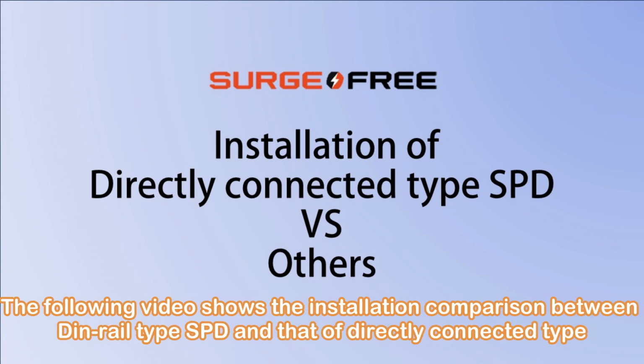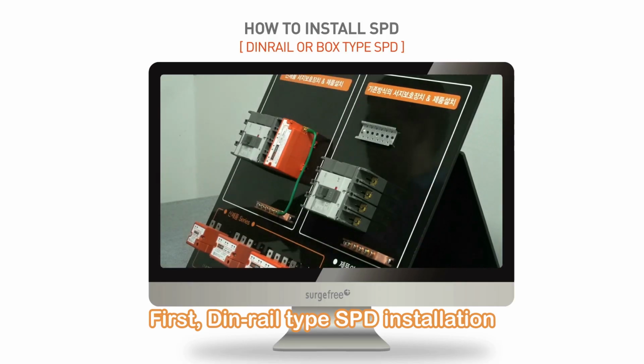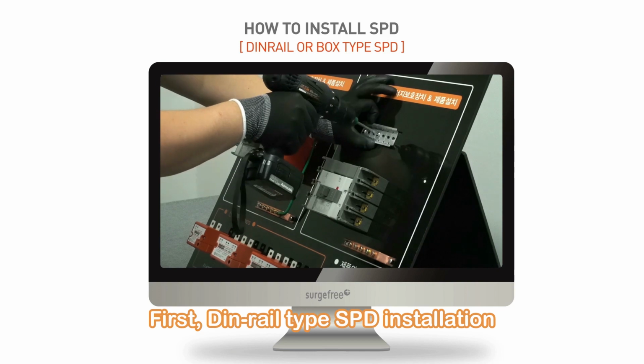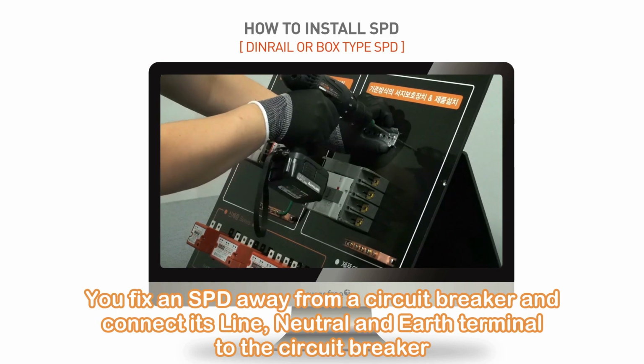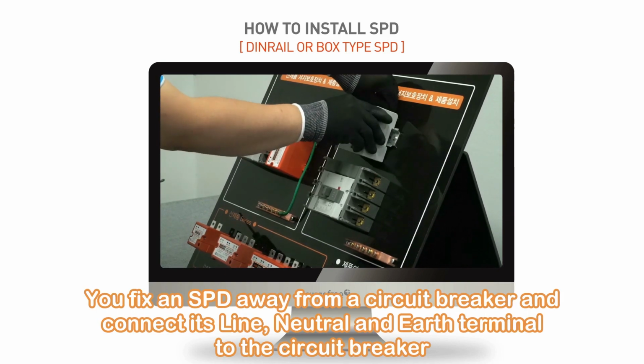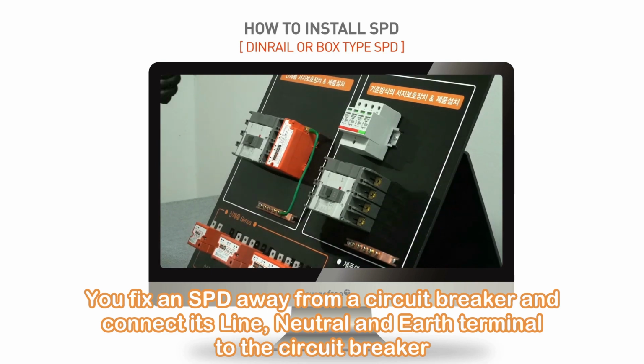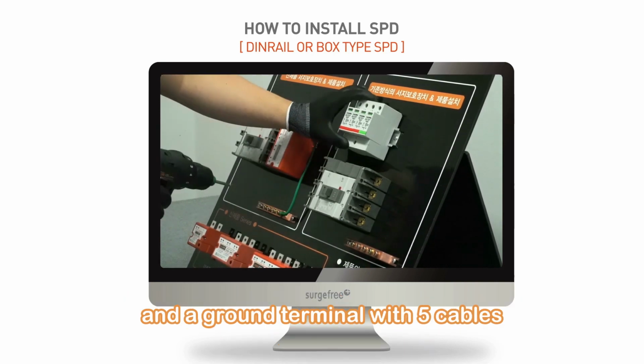The following video shows the installation comparison between DIN rail type SPD and the directly connected type. First, DIN rail type SPD installation: you fix an SPD away from a circuit breaker and connect its line, neutral and earth terminal to the circuit breaker and a ground terminal with 5 cables.